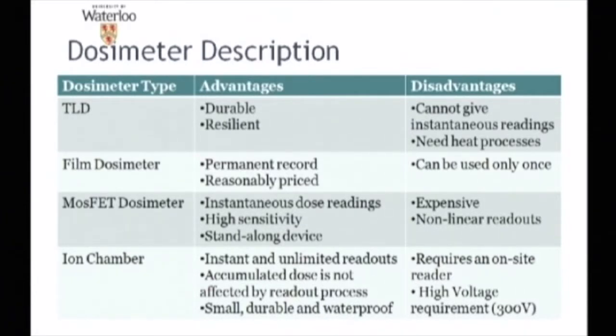Other ways of characterizing a LINAC machine involving a traditional X-ray film. So we would place an X-ray film underneath a LINAC machine, and profile could be generated from the image generated on the film dosimetry. The disadvantage is it's not really real time, and it can only be used once. Other newer technology involve integrated circuit technology such as the MOSFET dosimeter, which is a lot smaller. It gives real-time instantaneous reading, but the disadvantage is it's extremely expensive and the readout is extremely non-linear. It's dependent on humidity as well as temperature. So what works today might not give you the same reading tomorrow.